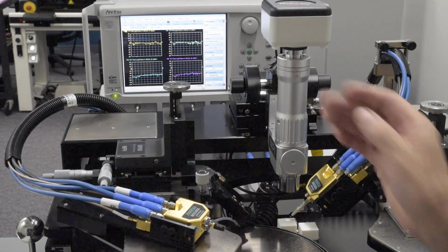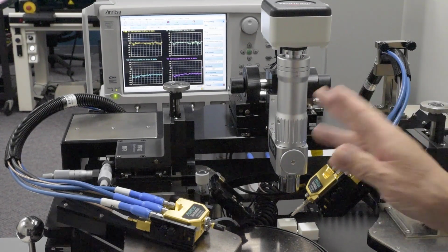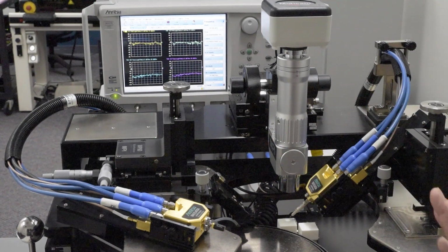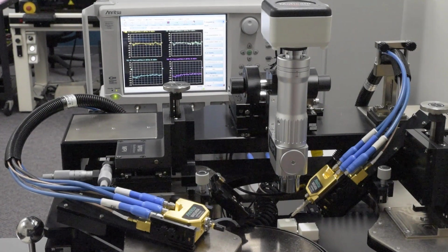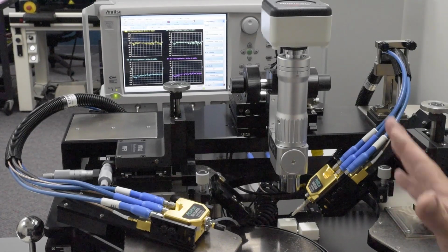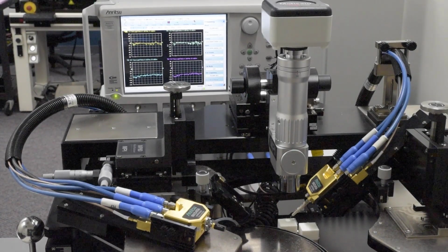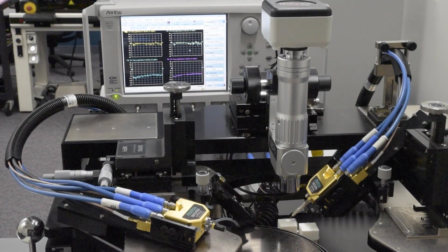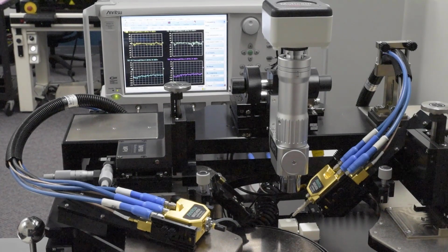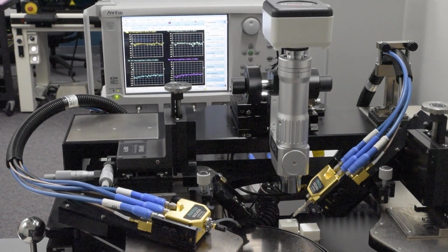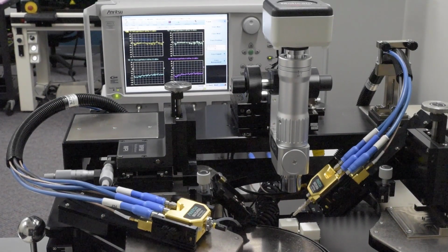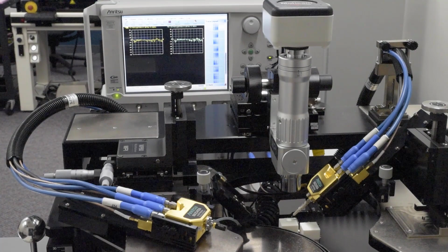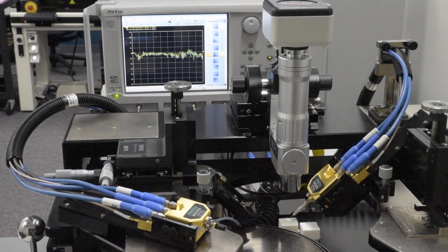So now port 1 is terminated with a short, and port 2 continues to have the probe mounted. On our display, we're showing S11 and S22, as well as S21 and S12. Now, the system right now is not calibrated, and you actually don't need a calibration in order to evaluate instrument stability. With the calibration not applied, I can take a look at S11 and S22 and evaluate that over time. But of course, the variations will make it a bit more challenging, and it'd be better if I normalize that. So if I want to start zooming in on this, I can first go to my trace menu and reduce the traces down to 2, so that I'm just looking at S11 and S22.